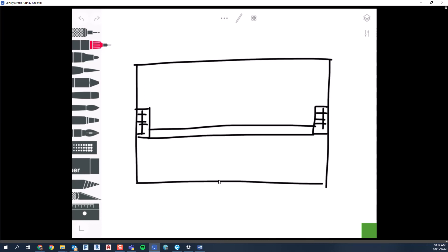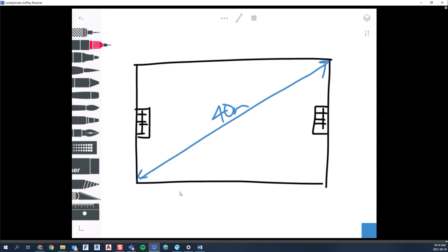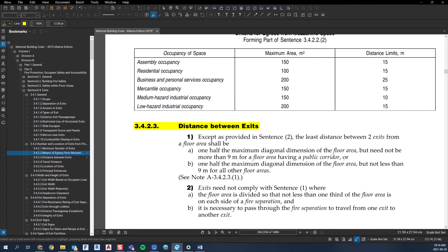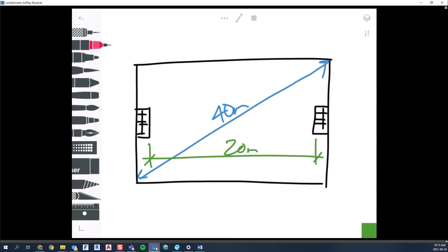Now let's look at a floor plate with no public corridor — say an office space where a tenant is taking the entire floor. They still need two exits. Going back to the diagonal dimension of 40 meters, we read sentence one: the least distance between two exits from a floor area shall be one half the maximum diagonal dimension of the floor area, but not less than nine meters, for all other floor areas. Half of 40 is 20 meters, and because there's no public corridor, the exits must be 20 meters apart.